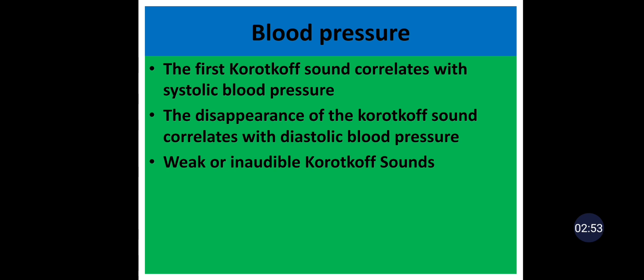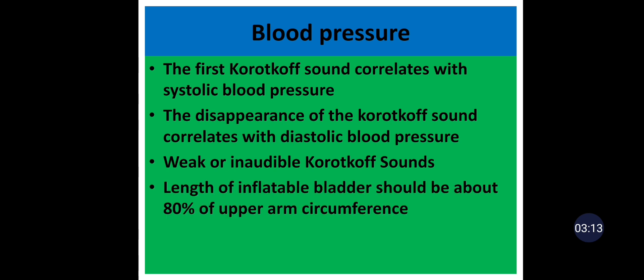The third reason is venous engorgement due to repeated inflations. To enhance the Korotkoff sound, raise the patient's arm before and while inflating the cuff. The fourth reason is due to shock. If the patient has a thready pulse and history of fluid loss or poor intake, it is definitely shock — so don't focus on the Korotkoff sound; just proceed to resuscitation.